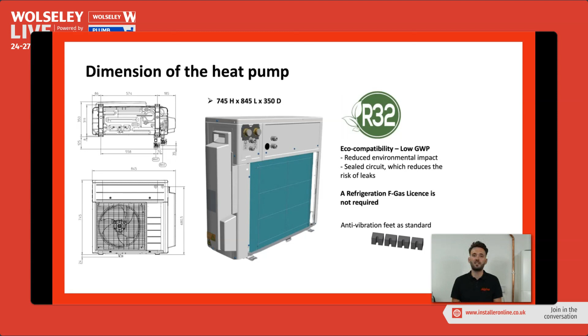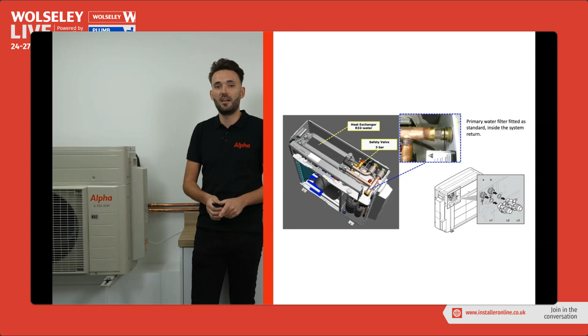So, internals of the unit, it's really simple. There's no pump in here. We're just using the pump that's already inside the combination boiler. But in here, we've got some little key features. We've got a little mesh filter. It's almost like a strainer on the return. This is a serviceable part. And with our valves, we can just valve off the unit, clean out the mesh filter, pop it back in. It just helps with a little protection to the system.